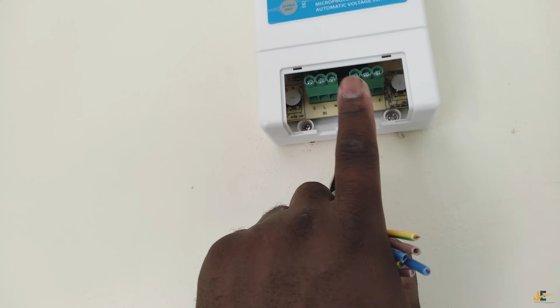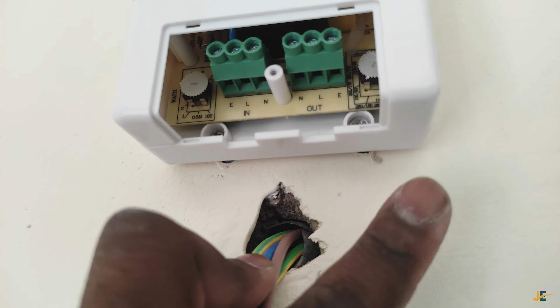So for proper termination, I have to mark my supply cables and my load or output cables, then go ahead and terminate them. In is the supply from the circuit breaker, which is 32 amperes for my power circuit, and the output will go direct to my power socket outlets.